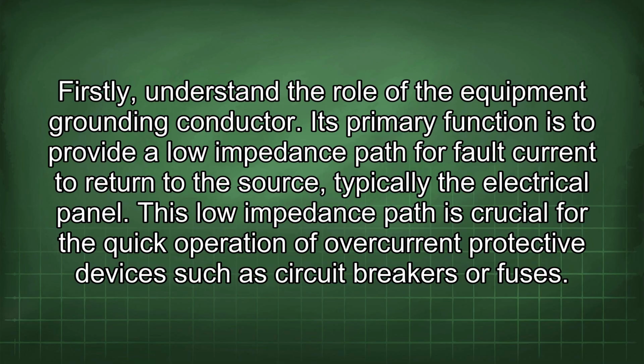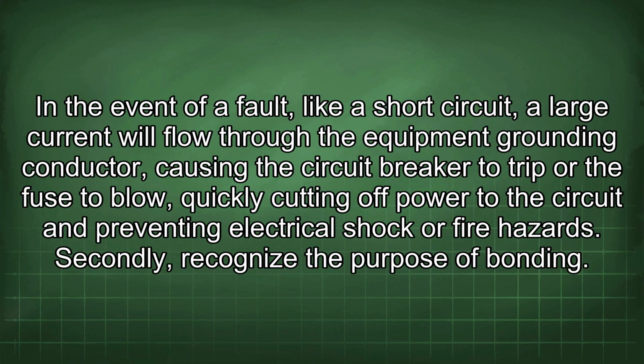Its primary function is to provide a low impedance path for fault current to return to the source, typically the electrical panel. This low impedance path is crucial for the quick operation of overcurrent protective devices such as circuit breakers or fuses. In the event of a fault, like a short circuit, a large current will flow through the equipment grounding conductor, causing the circuit breaker to trip or the fuse to blow, quickly cutting off power to the circuit and preventing electrical shock or fire hazards.